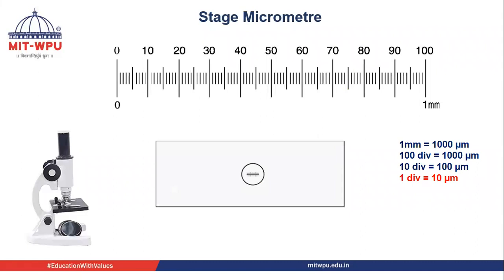So each division of this stage micrometer is 10 micrometers. The stage micrometer we are using has a one millimeter scale with 100 divisions, and each division is equal to 10 micrometers.